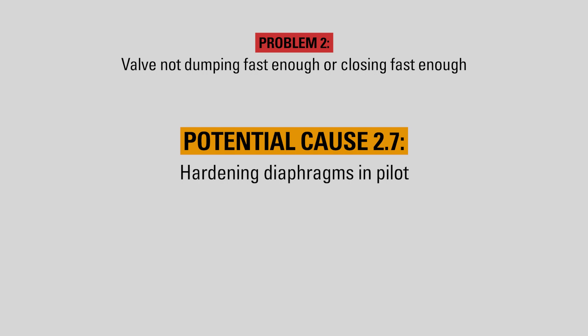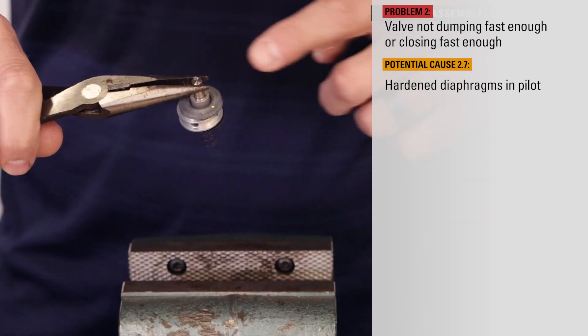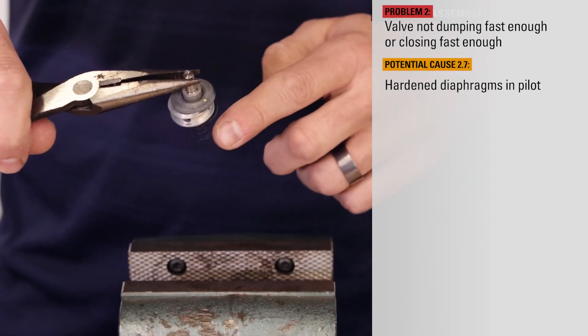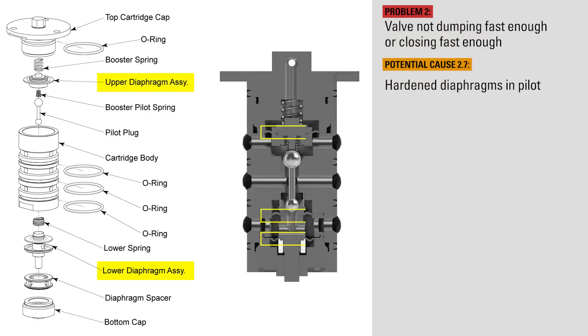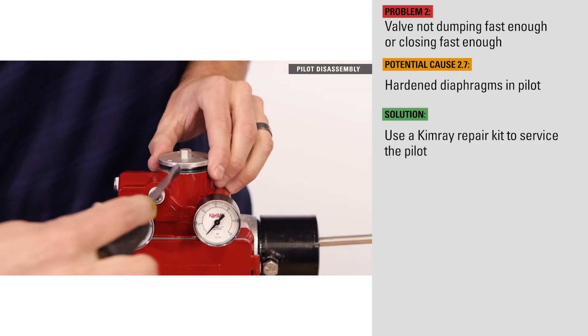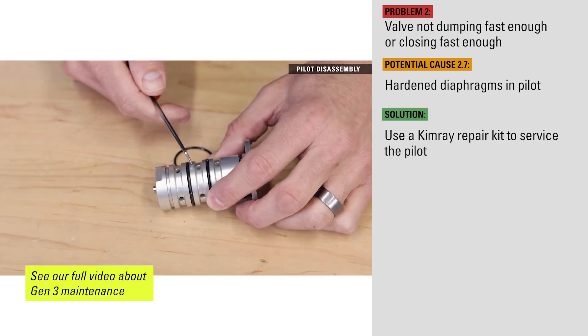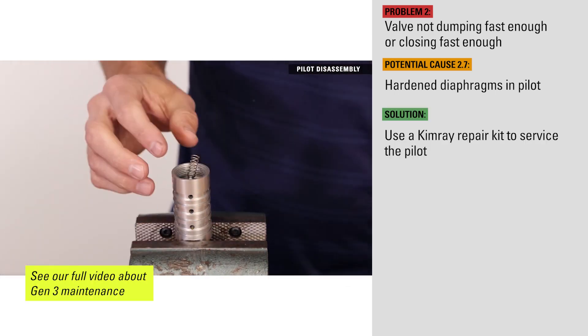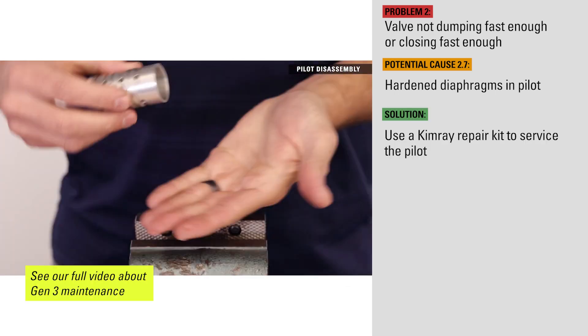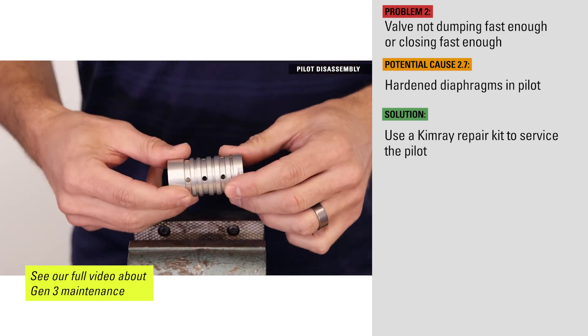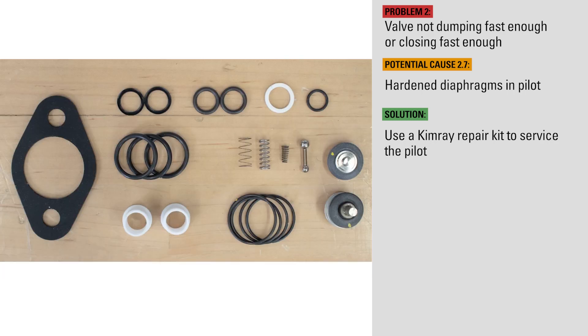If the controller has been in service for a long time without the elastomers being replaced, the diaphragms in the pilot may have stiffened to the point that they won't fully flex. If you suspect this is the case, remove the pilot from the controller, disassemble, and replace all the elastomers. Kimray offers full repair kits containing all soft components that should be replaced at regular service intervals.